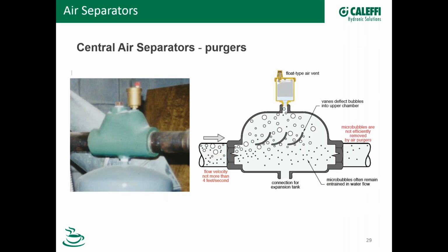Okay, let's move to air separators. A purger is a type of central air separator that's semi-effective in removing larger bubbles, only at low velocities though, and it does not remove microbubbles. So it relies on the buoyancy of the bubbles to actually remove the air. And what did you say, Bob? It's like the rotary phone of central air separators. It's kind of outdated, but we still see them out there.